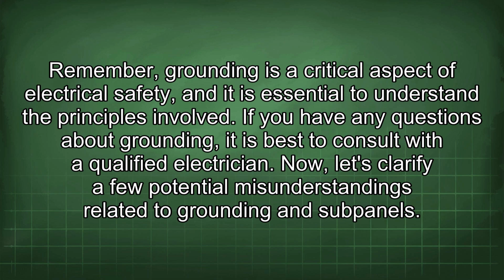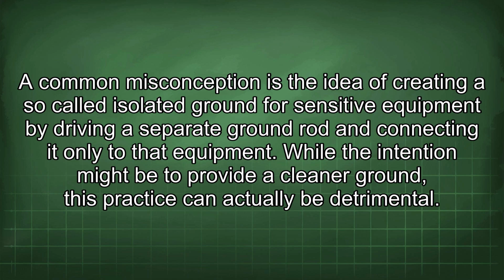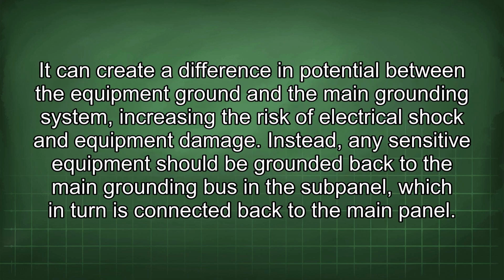Now let's clarify a few potential misunderstandings related to grounding and subpanels. A common misconception is the idea of creating a so-called isolated ground for sensitive equipment by driving a separate ground rod and connecting it only to that equipment. While the intention might be to provide a cleaner ground, this practice can actually be detrimental. It can create a difference in potential between the equipment ground and the main grounding system, increasing the risk of electrical shock and equipment damage. Instead, any sensitive equipment should be grounded back to the main grounding bus in the subpanel, which in turn is connected back to the main panel.